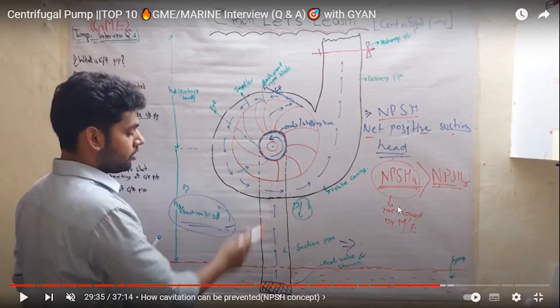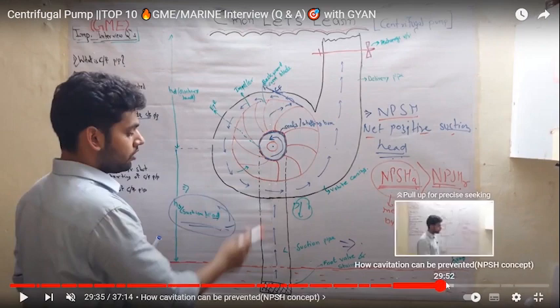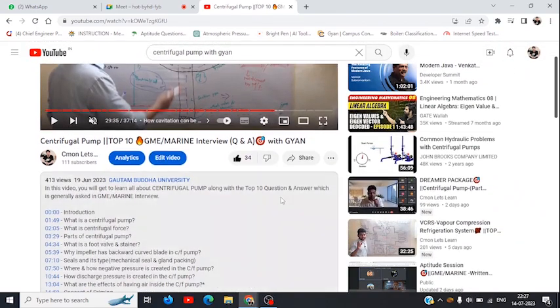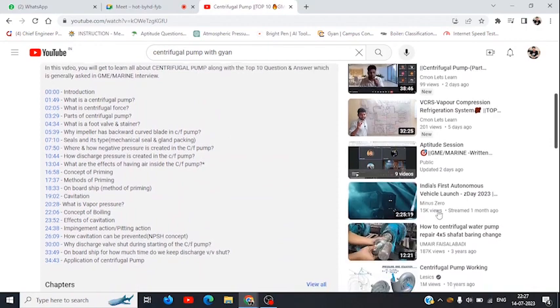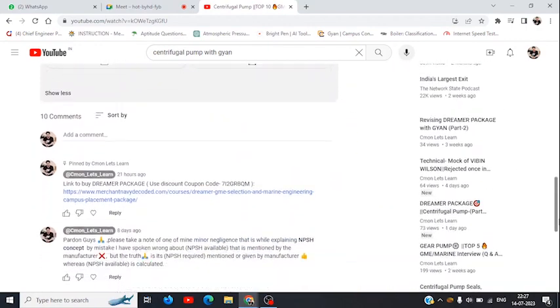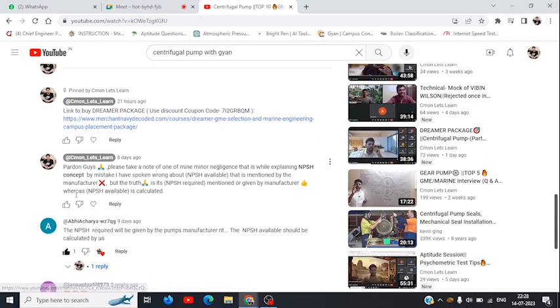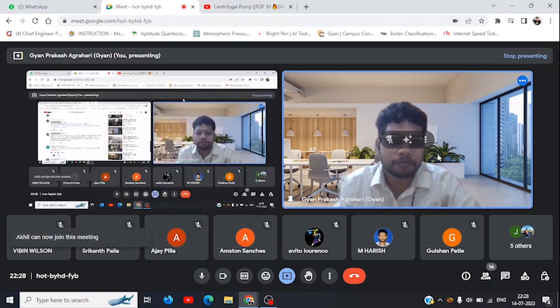I did it by mistake. Everyone, notice what mistake I made. Pardon me, guys, please take note of one of my minor negligences. While explaining the NPSH concept, I mistakenly said NPSH available is mentioned by the manufacturer, but the truth is NPSH required is the one given by the manufacturer, whereas NPSH available is calculated. Clear? Got it?